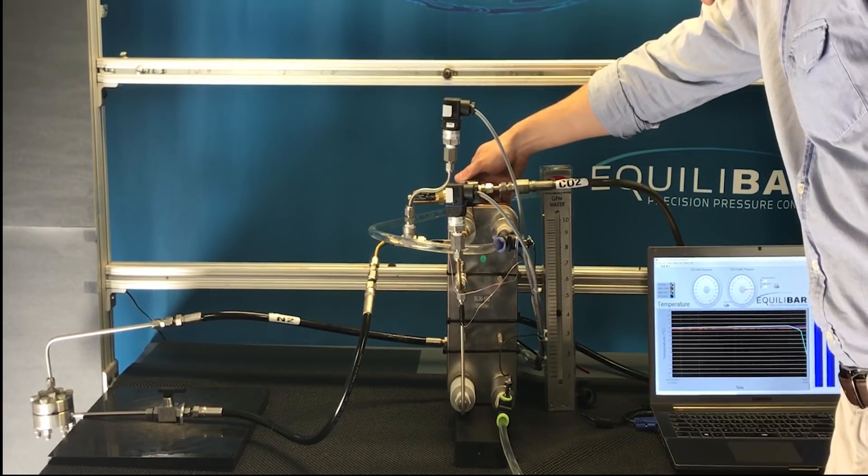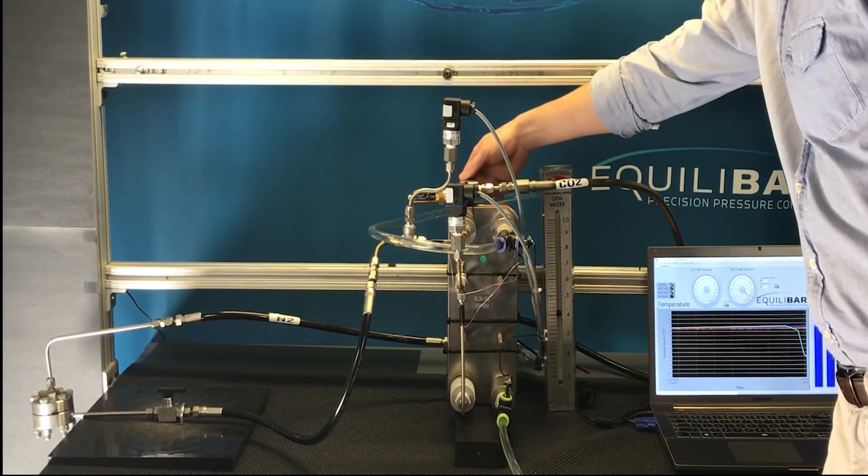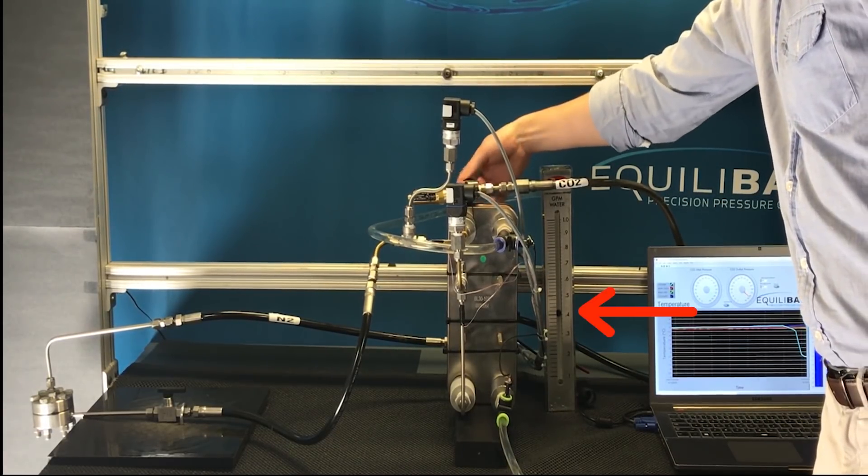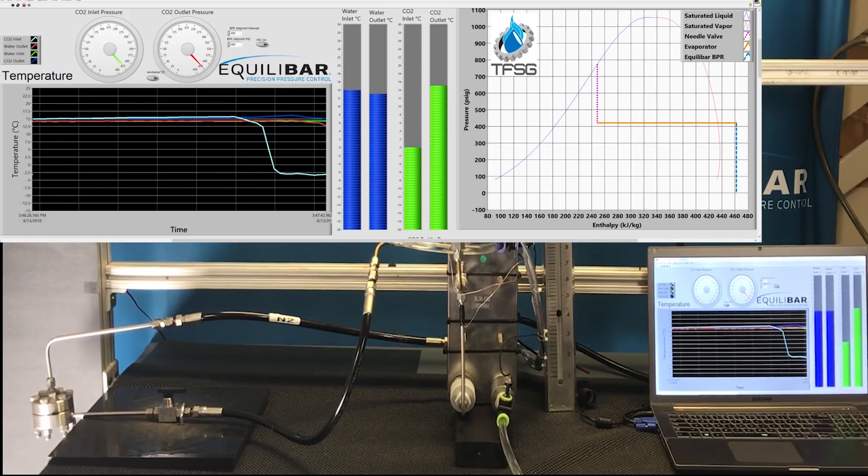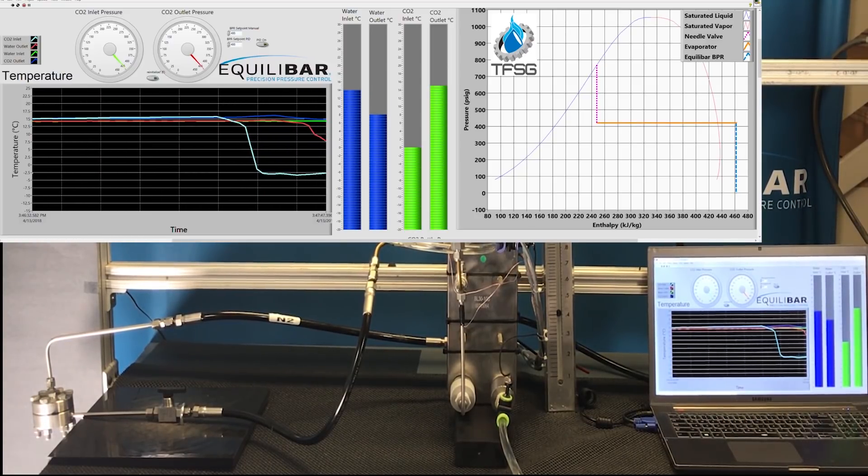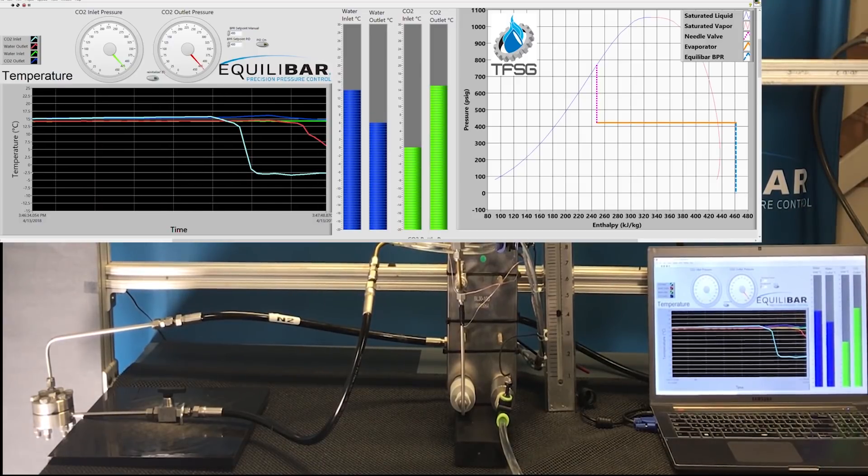I will run the process again but this time the heat load flow rate will be doubled to 0.4 GPM to show how the Equilibar can maintain pressure control with varying heat loads. It is expected during this run that the convergence time will take a little bit longer to reach equilibrium. This convergence time could be used to back calculate the heat transfer rate.